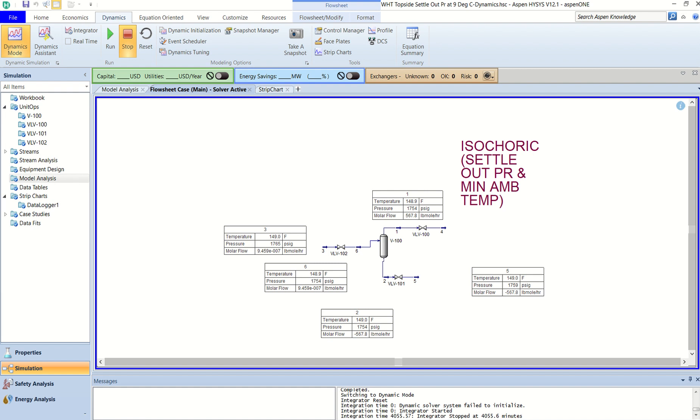Suppose we are talking about more conservative winter conditions because we are calculating MDMT. MDMT being say minus 90 degrees Celsius, and the vessel will come into equilibrium with the ambient conditions. Subsequently, the pressure inside the gas will go down due to the condensation of the gas.